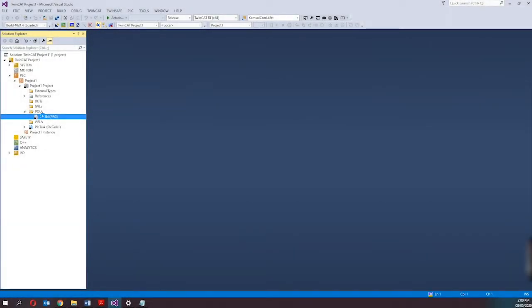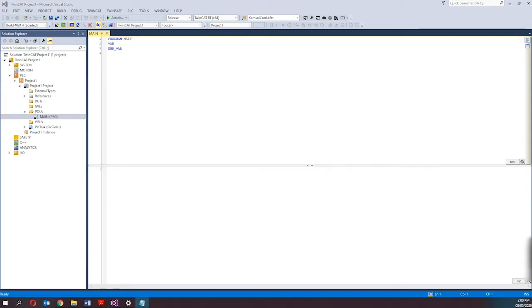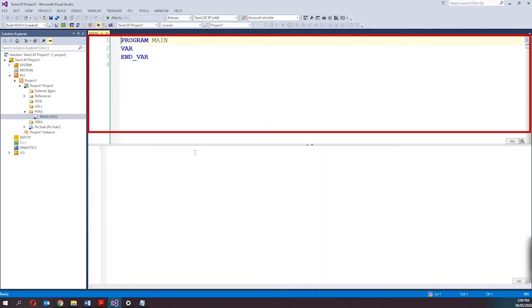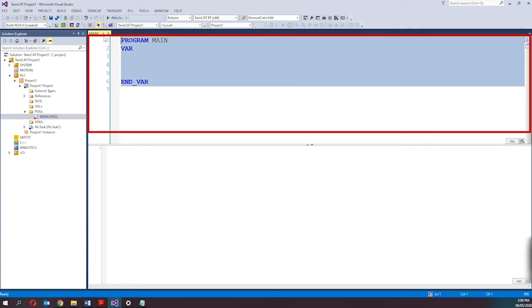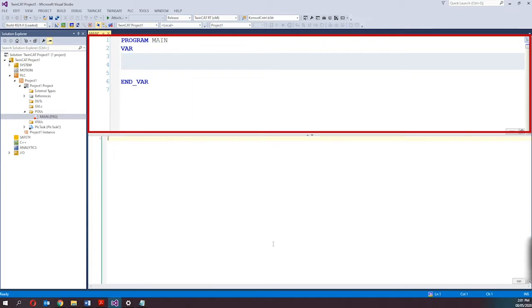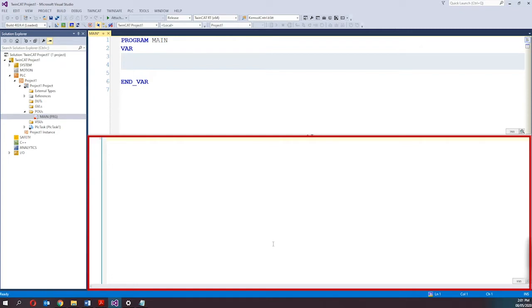First, in the declaration part of the POU. Here in my Project 1 PLC project, to go to the declaration area of the POU, just click on the POUs folder dropdown and you'll see a MAIN PRG, which is the main program. Double click on it and the main program editor window will open. The editor window has two areas: the upper part is where I can declare local variables for use inside the main program. By default, the keywords VAR and END_VAR are already available for local variable declaration, and variables can be declared between those two keywords. The lower part of the window is where I can do my programming using any language — whether it's ladder logic, structured text, FBD, CFC, or SFC.